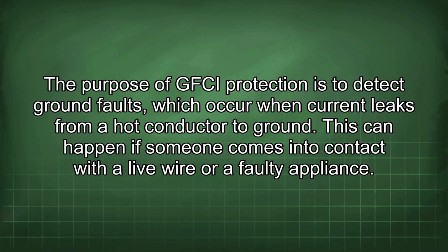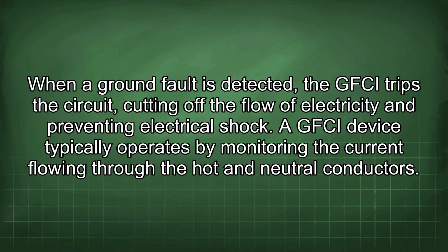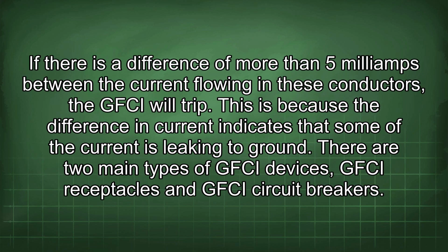The purpose of GFCI protection is to detect ground faults, which occur when current leaks from a hot conductor to ground. This can happen if someone comes into contact with a live wire or a faulty appliance. When a ground fault is detected, the GFCI trips the circuit, cutting off the flow of electricity and preventing electrical shock. A GFCI device typically operates by monitoring the current flowing through the hot and neutral conductors. If there is a difference of more than 5 mA between the current flowing in these conductors, the GFCI will trip. This is because the difference in current indicates that some of the current is leaking to ground.